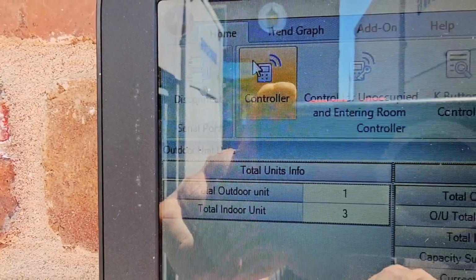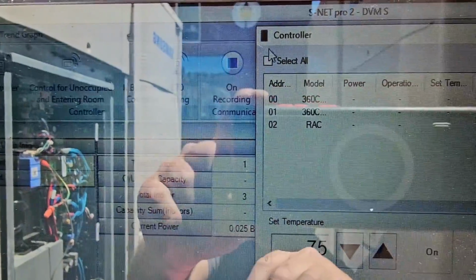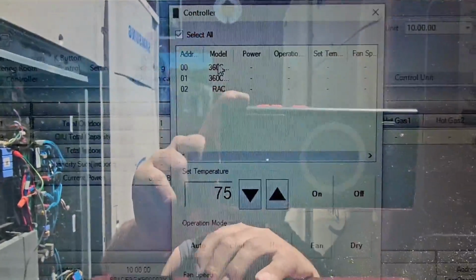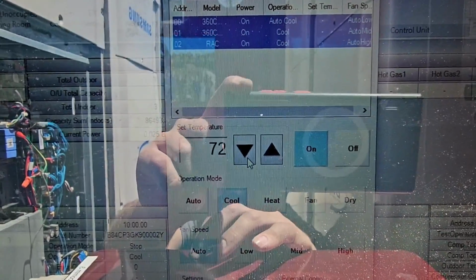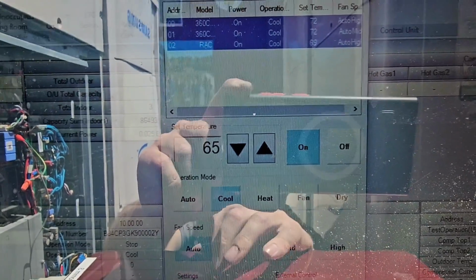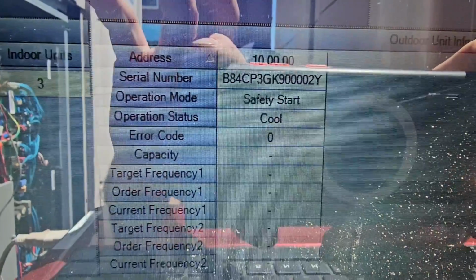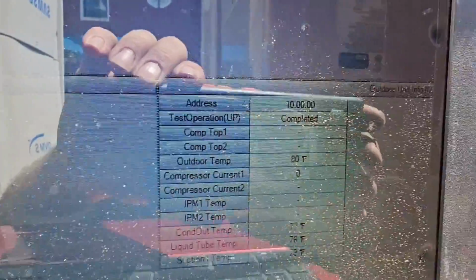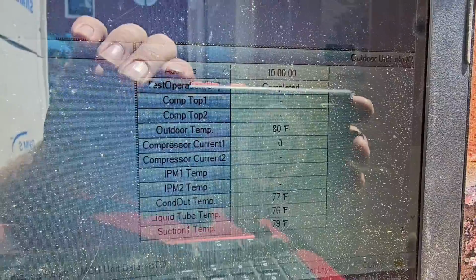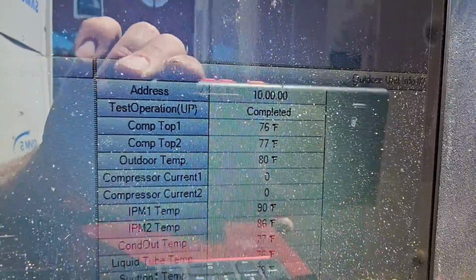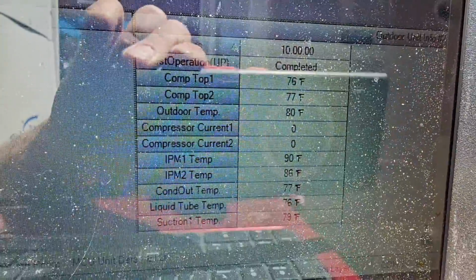I'm going to go back up here to the controller, select all 3 indoor units, and then on cooling, turn the temperature down to 65, and then exit. Operation status cool. Operation mode was stop. You just saw it change to safety start. Still not displaying those top sensors for the compressor, but looks like they're about to, yep, so now they're reading correctly, 76 and 77. I'm so excited. All right.